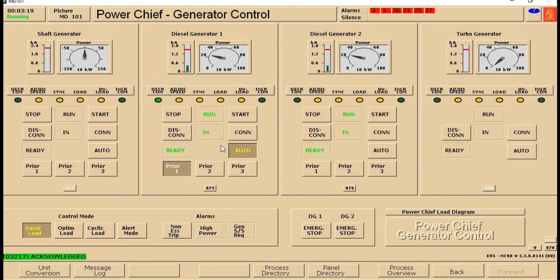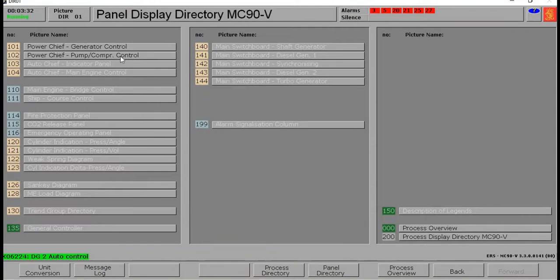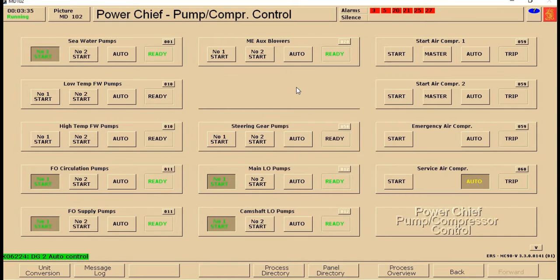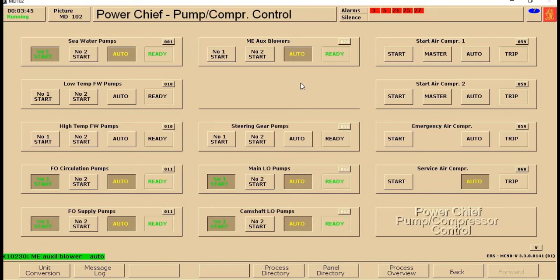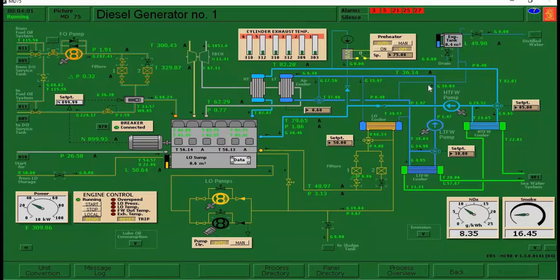Generator control. So our diesel generator 1 is in priority number 1, so we'll put our diesel generator 2 into priority number 2 and click auto. After that, we'll go to the pump control, and all of our running pumps here, we need to put into auto. Okay, seawater, FO supply, camshaft, main lube oil. Okay, so after putting every running pump into auto, now we will just monitor our diesel generator 1 and diesel generator 2. Okay, diesel generator 1.